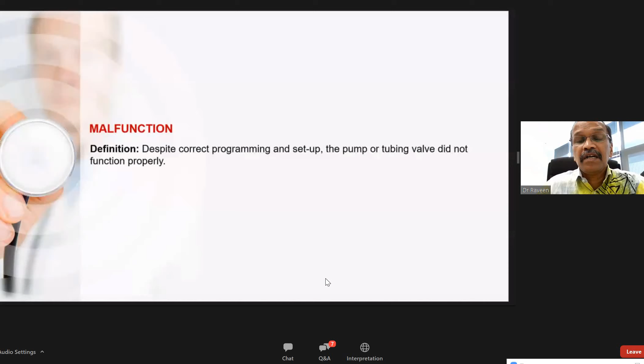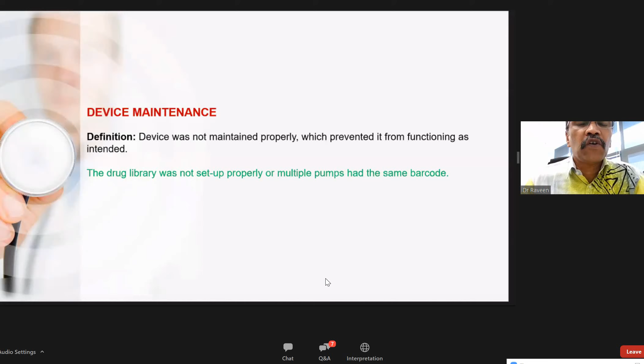Maintenance of device. All these pumps need to be serviced regularly. Why it needs to be serviced is to allow it to function as it was intended to do. The drug library might not have been set up properly. There might be multiple pumps with the same barcode attached, so we have to be careful. So this is the maintenance. If you don't maintain your pump, the calibration can run off, and even if you key in the correct values, it will give more or less than what was intended. So we need to follow the recommendation of the supplier, the manufacturer, to do the maintenance. There are some pumps which need yearly maintenance, and some which need 6 monthly maintenance. So we need to follow the manufacturer's guideline on this.